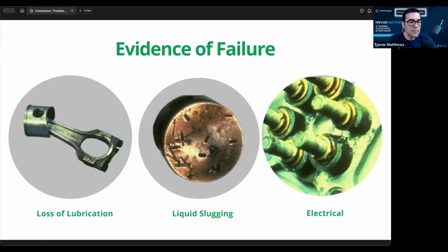Pulling a deep vac is so important, because if you get moisture in the system and your liquid line filter dryer doesn't pull it all out, what can happen? Well, I have seen it where it copper coats everything. There'll be an acid in there, to the point where the copper tubing runs through and it'll absolutely take the valve plates and the pistons and cylinder walls and copper coat them from the acid that's left in the system as far as moisture. Yeah. So what happens is that POE oil breaks down because moisture is added to it. POE oil is made of organic acid and alcohol, and when you introduce water or moisture back to it, it brings it back to that state. And so if you ever pull off a head and you see that copper on there, you didn't get all the moisture out of the system.